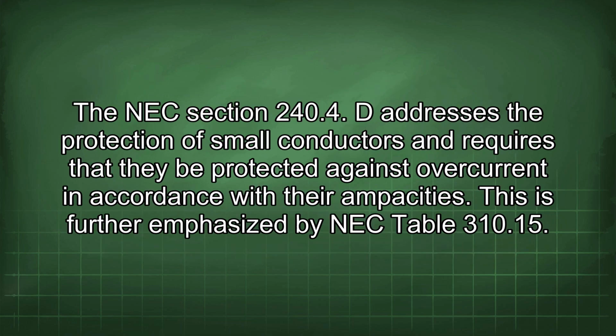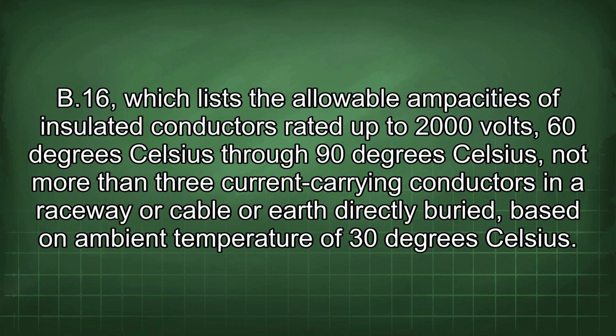The NEC Section 240.4(D) addresses the protection of small conductors and requires that they be protected against overcurrent in accordance with their ampacities. This is further emphasized by NEC Table 310.15(B)(16), which lists the allowable ampacities of insulated conductors rated up to 2000 volts, 60 degrees Celsius through 90 degrees Celsius, not more than 3 current-carrying conductors in a raceway or cable or earth directly buried, based on ambient temperature of 30 degrees Celsius.